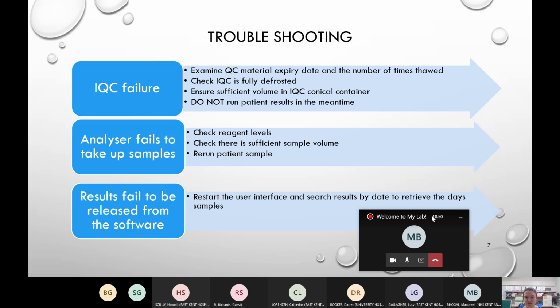If the QC had also been frozen and defrosted too many times, that could cause it to expire or not produce accurate results. Also, another example would be when sometimes the results weren't released from the software, which was a bit frustrating. In that case, it was just a simple turn it off and back on again kind of problem, which sometimes is just the thing we need to do within the lab.